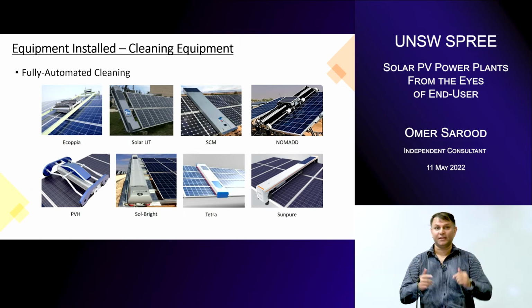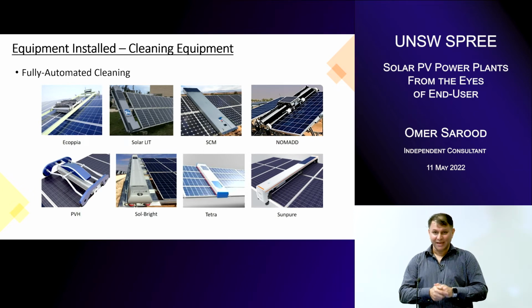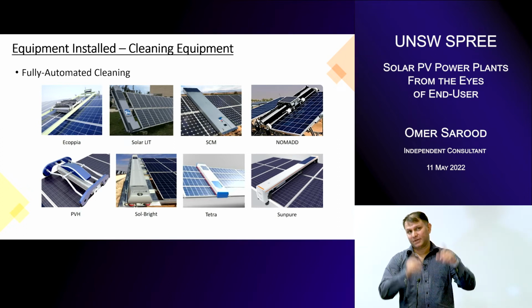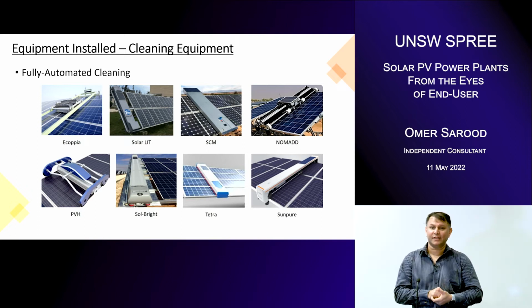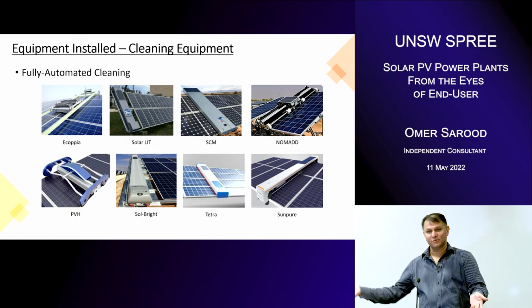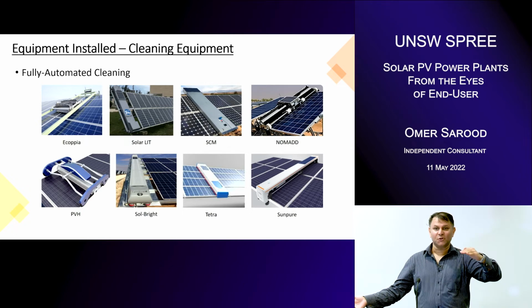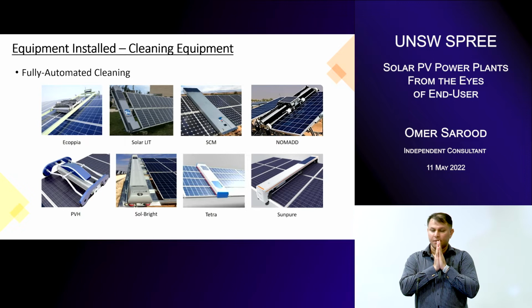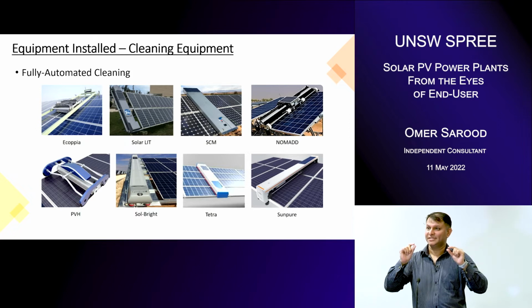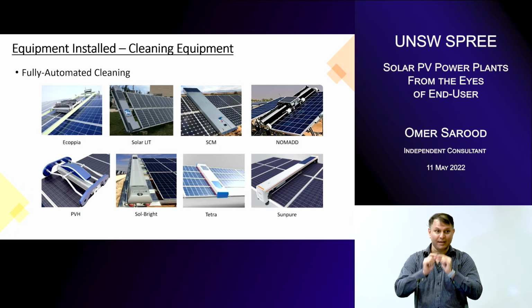Unless someone can think of something, and I know some companies are working in this direction as well, because in these deserts, if it's closer to the sea, there's a lot of humidity. And that is becoming a big problem for dry robotic cleaning of modules. The moment the humidity goes above a certain percentage, sorry, I'm not at liberty to share that at the moment, it becomes a problem. Dry cleaning cannot work. So what do you do? You stop the cleaning process. When you stop the cleaning process, the modules remain dirty. Generation is low. No matter how high the efficiency of a solar module is, guys, it's covered with millimeters of sand.